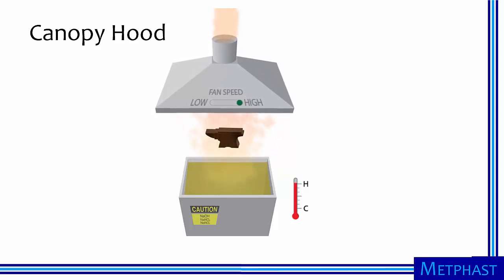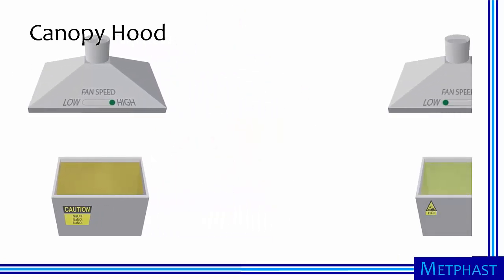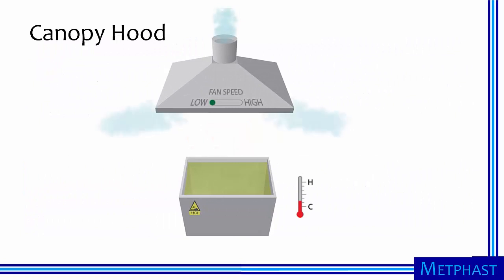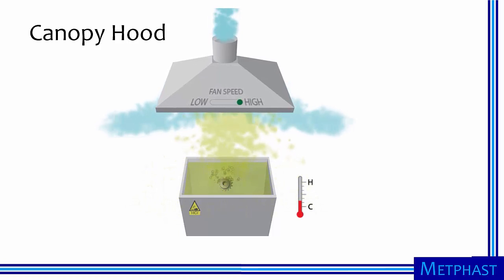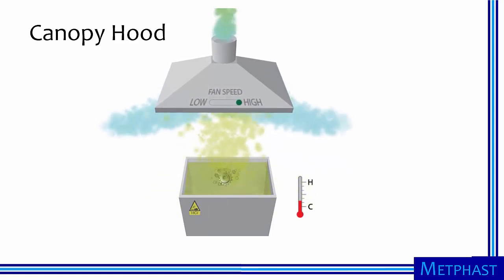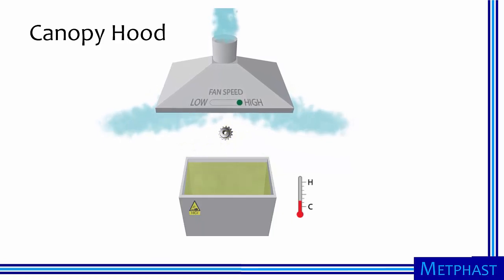Canopy hoods are not recommended for cold processes, or those that emit vapors that are more dense than air. When a steel gear is dipped in room temperature hydrochloric acid in descaling, the heavier-than-air vapors do not rise to meet the canopy hood. If possible at all, much higher fan speeds are needed to capture these vapors, perhaps ten times or more than the hot process.